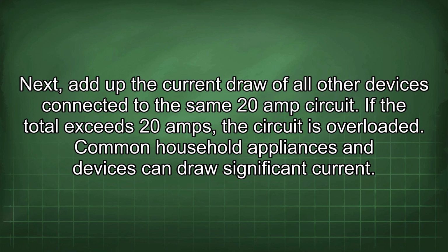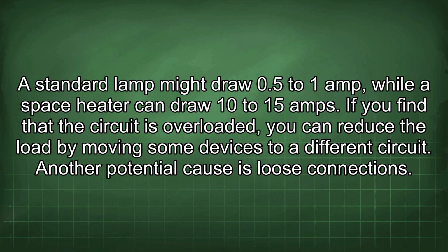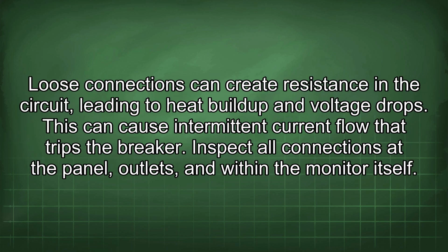Common household appliances and devices can draw significant current. A standard lamp might draw 0.5 to 1 amp, while a space heater can draw 10 to 15 amps. If you find that the circuit is overloaded, you can reduce the load by moving some devices to a different circuit. Another potential cause is loose connections. Loose connections can create resistance in the circuit, leading to heat buildup and voltage drops.